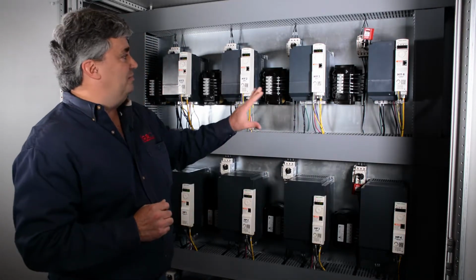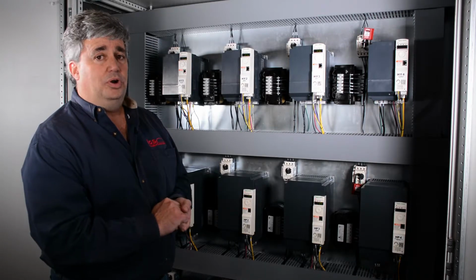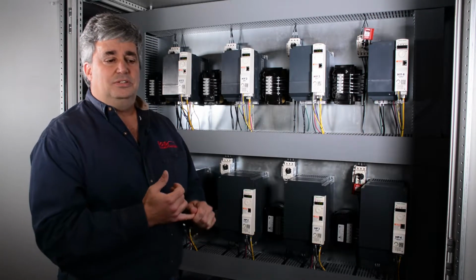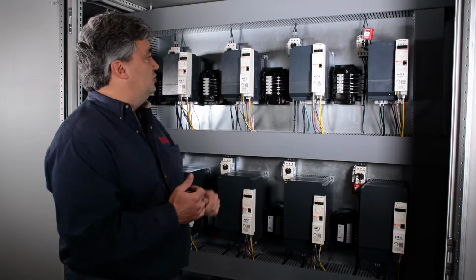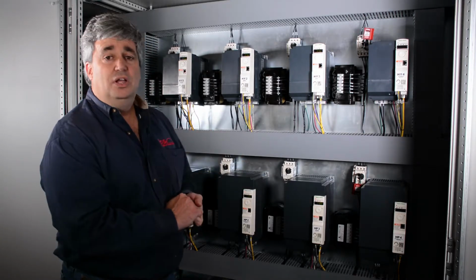The other thing we do in a VFD panel that is very important: heat is the biggest cause of failure with VFDs, so we air condition these panels.